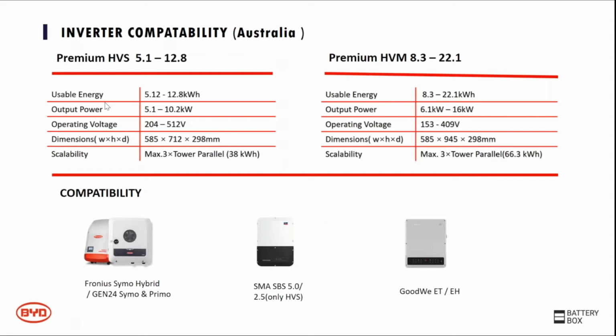Just some key parameters here. For HVS, the usable energy ranges from 5.1 kilowatt hours to 12 kilowatt hours battery, and the output power is only from the DC side, the battery side - it obviously depends on the inverter. The operating range is from 200 volts to 500 volts. The dimension is actually a very slim battery, only 300 millimeters deep, and scalability is up to 3 towers in parallel.